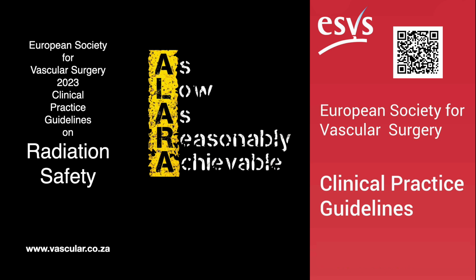Okay. Optimizing the beam itself. 2, image processing algorithms. Sophisticated software that cleans up the image after it's acquired. This includes things like automatic pixel shifting to compensate for motion, temporal averaging, spatial noise reduction algorithms, image enhancement techniques. Making a lower dose image look better. Essentially, yes. 3, hardware configurations. Optimizing the entire imaging chain from source to detector for better efficiency.